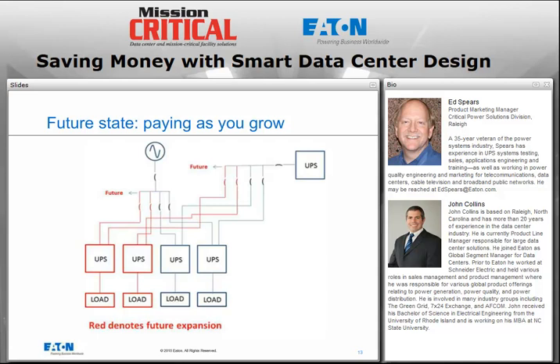And the primary UPS is going to react to that fault by quickly transferring to its bypass. And in this case, its bypass is the utility fed through the catcher system, so we have a much better chance of supplying the necessary instantaneous current to clear that downstream fault. Whereas if I took a UPS output and transferred it to simply another UPS inverter output, the ability of those two UPSs in series to clear the fault would be extremely limited. So flexibilities like that are going to be the hallmark of providing better availability and better fault tolerance for the client's final system as configured.